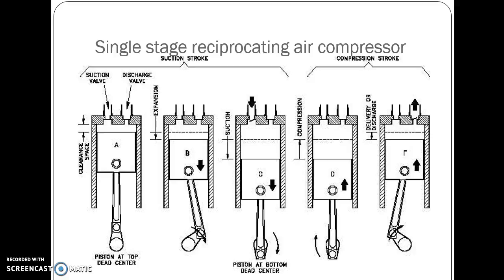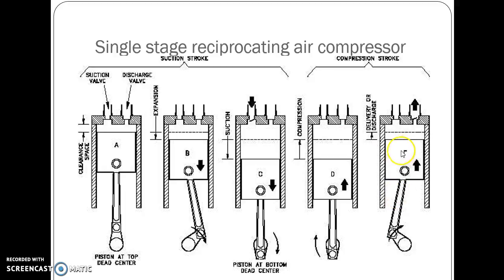The working of a single stage reciprocating air compressor is shown here. Three diagrams show the suction stroke and two diagrams show the compression stroke. In the first diagram, the piston is at the top dead center and both suction and discharge valves are closed. In the next diagram, the piston moves from top dead center toward the bottom dead center. In the third diagram, the piston reaches the bottom dead center and the suction valve opens. During the compression stroke, the piston moves from bottom dead center back to the top dead center, where the discharge valve opens. This is how the single stage compression works.